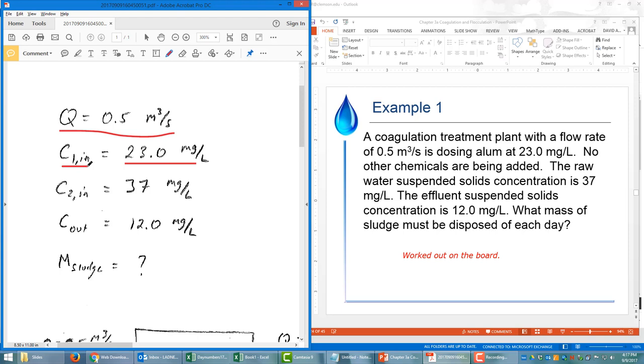Dosing alum at 23 milligrams per liter, we're going to call that C1,in. No other chemicals are being added, but the raw water suspended solids does have a concentration of 37 milligrams per liter, we'll call that C2,in, and the effluent suspended solids concentration is 12 milligrams per liter, we'll call that Cout.